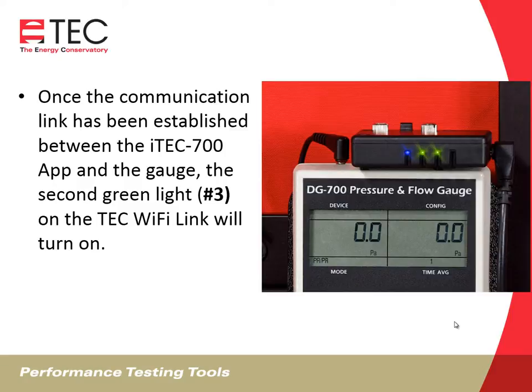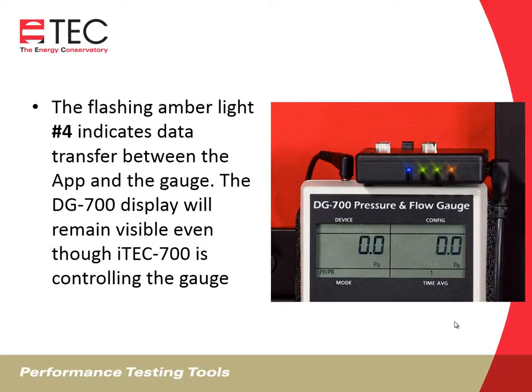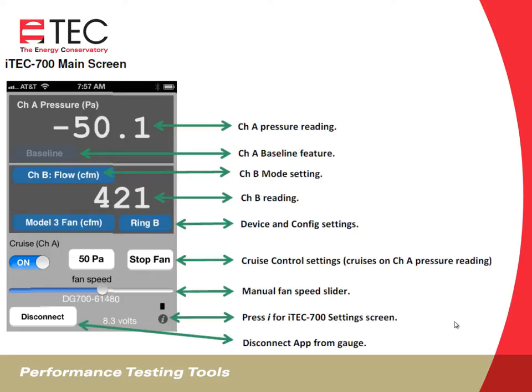Once the communication link is established between the iTEC-700 app and the gauge, the second green light — number three — on the TEC Wi-Fi Link will turn on. The flashing amber light, number four, indicates data transfer between the app and the gauge. The DG700 display will remain visible even though the iTEC-700 is controlling the gauge. On the iTEC-700 screen, channel A shows building pressure with reference to the outside. Channel B can be in either flow mode or pressure-pressure mode, displaying the channel B flow depending on the fan model and ring configuration. You also have a cruise control button, a quick stop button, and a manual fan speed slider. There is also a disconnect button that disconnects the software from the gauge.